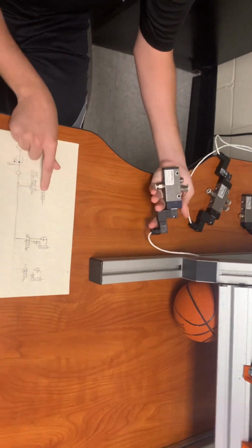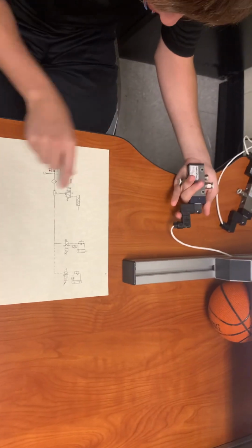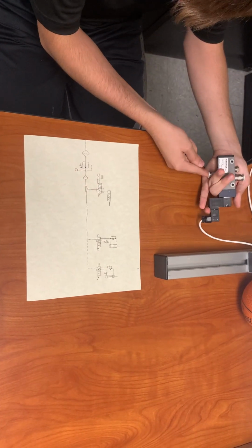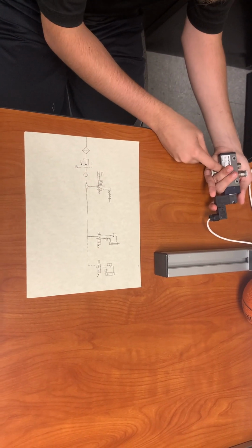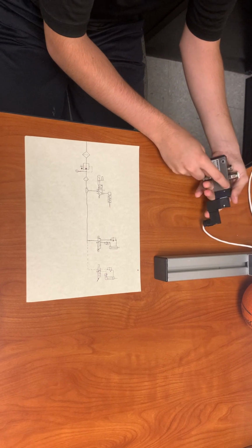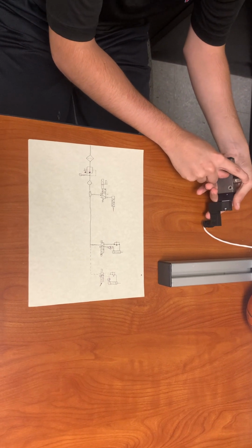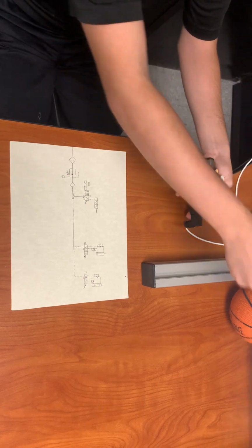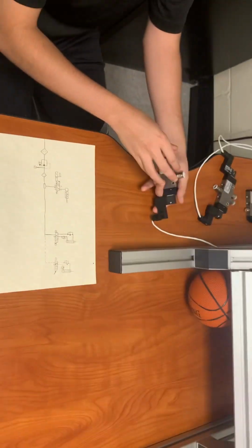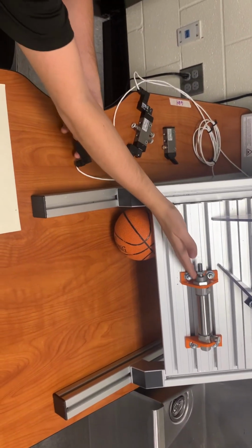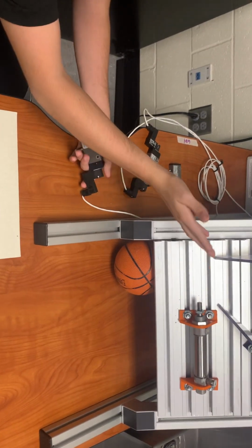our single acting cylinder. For this first valve, we use the number 1 port as a supply port, feeding air into the cylinder, and it flows through to our number 2 port on the top of the valve. This port right here connects to our single acting cylinder and actuates the cylinder rod forward, so it's always at an extended position.